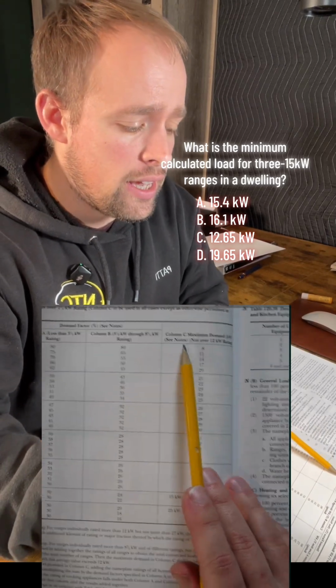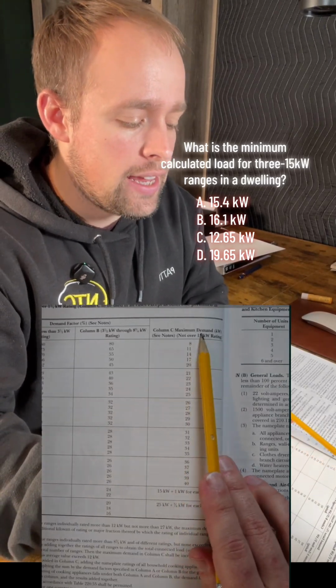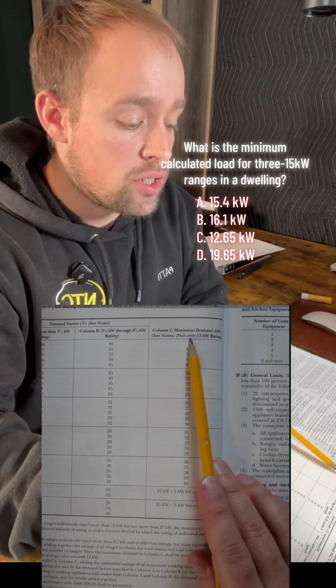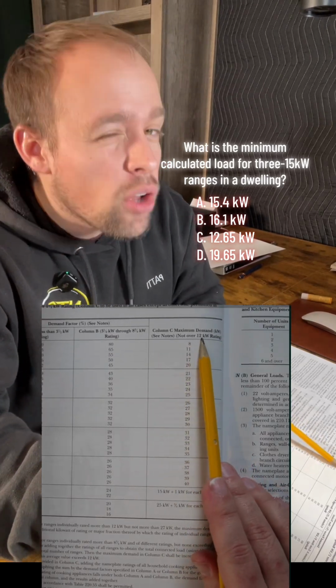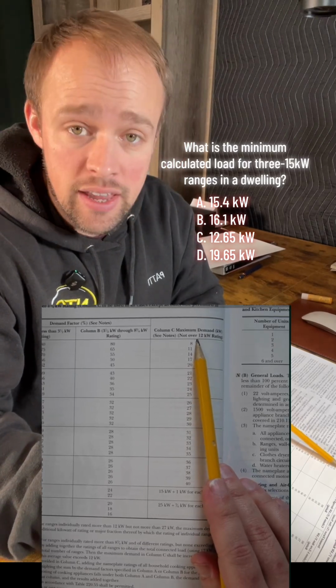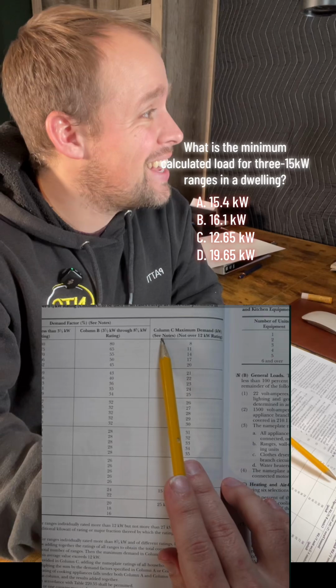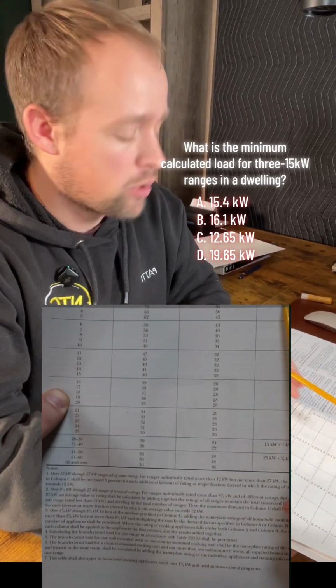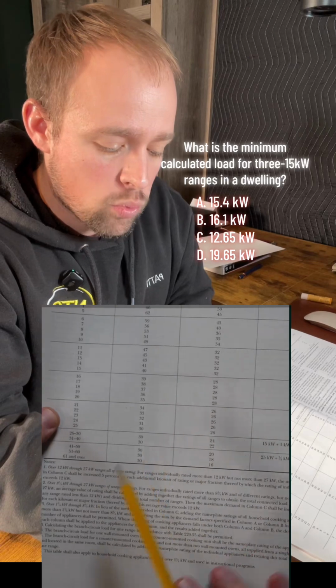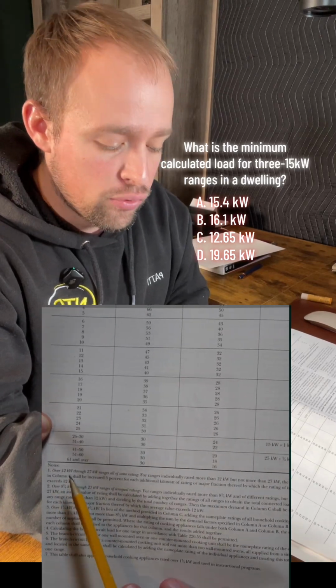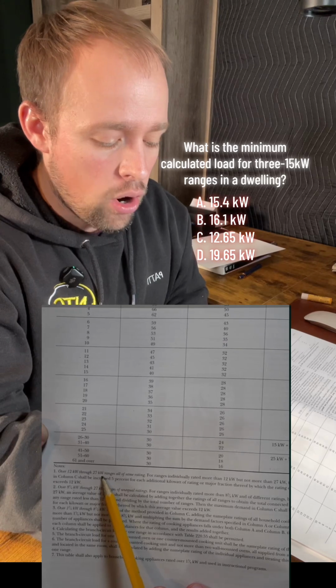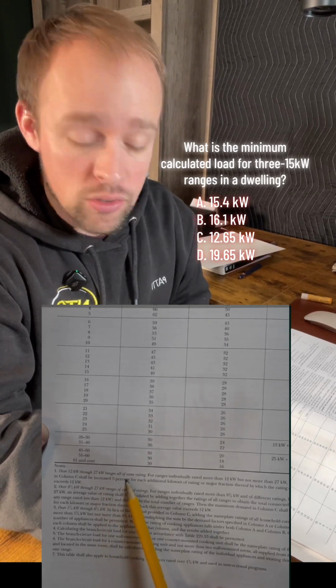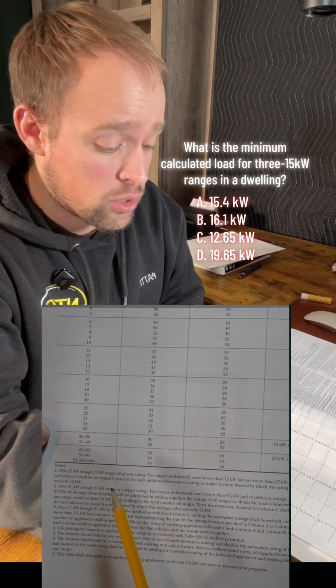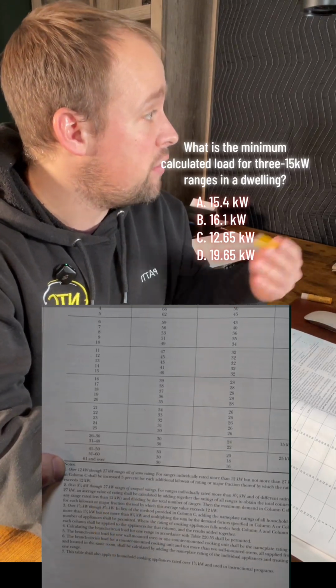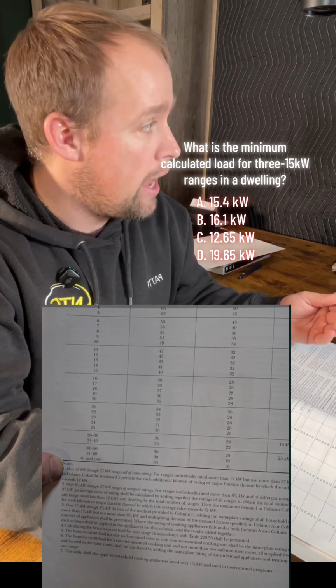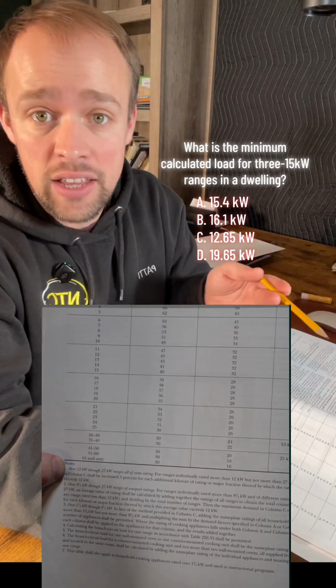And then column C is maximum demand in kW for ranges not over 12 kW, but our ranges say 15 kW. So now what do we do? Notice how it says C note, so that's exactly what we're going to do. So note 1 says we're over 12 kW through 27 kW, and all of the ranges are the same rating. So this is the note that we're falling under, okay, because we're over 12. Our question says three 15 kW ranges, and all of those three are 15. They're all the same rating.